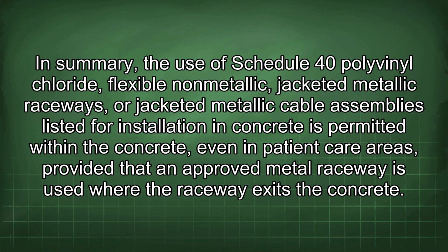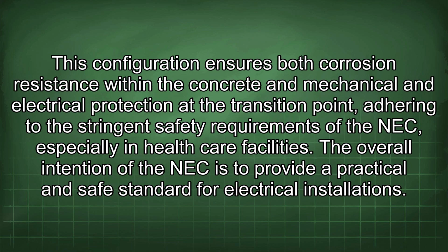In summary, the use of Schedule 40 polyvinyl chloride, flexible nonmetallic, jacketed metallic raceways, or jacketed metallic cable assemblies listed for installation in concrete is permitted within the concrete, even in patient care areas, provided that an approved metal raceway is used where the raceway exits the concrete. This configuration ensures both corrosion resistance within the concrete and mechanical and electrical protection at the transition point, adhering to the stringent safety requirements of the NEC, especially in health care facilities.